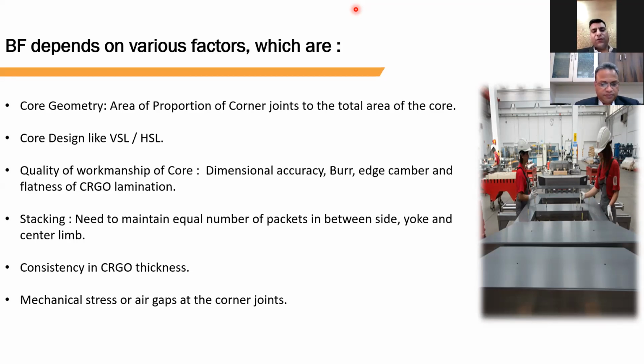Ultimately, we need to create a closed loop in our core. That's why we do all this R&D in design. If our CRGO is perfect, our handling is perfect, everything is perfect, but our dimensions are not perfect, then any deviation in dimensions will create a gap between joints. And if there are air gaps, flux will dissipate from that area, the loop will be disrupted, and we will not get optimum utilization of that core.